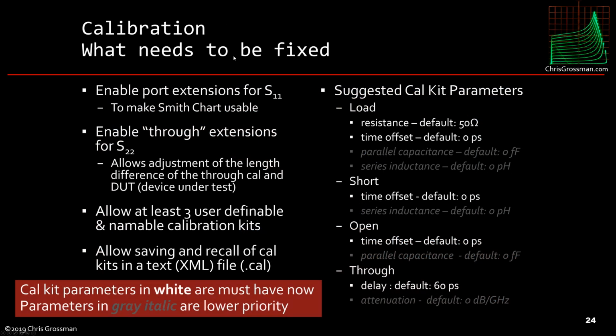Anyway, so what needs to be fixed for the calibration? One, they need to enable port extensions for S11 to make the Smith chart usable. They should also enable through extensions for S22. That will allow for the adjustment of length difference between the through cal and the device under test.